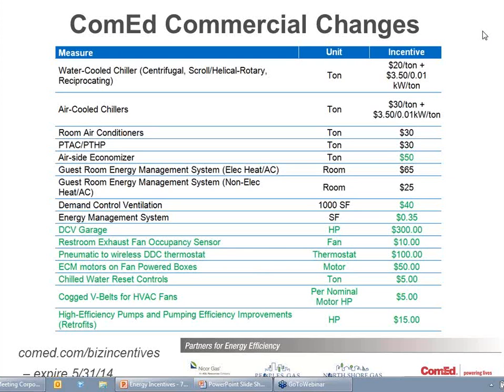Guest room systems for hotels, there's rebates for those kind of controls. Demand control ventilation used to be 3 cents per square foot. Now it is 4 cents per square foot. So it has increased a little bit, and you can double dip it with the gas utility. So if you're getting 50 cents a square foot from the gas utility plus 4 cents for ComEd, you're really getting 54 cents for the CO2 sensors.